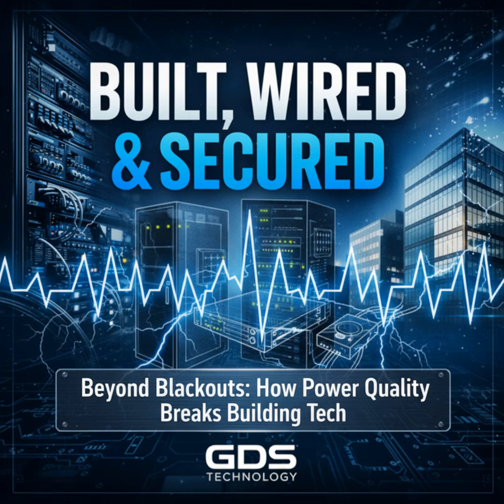Are there common mistakes you see when teams choose the wrong approach? Yes, the classic is treating the symptom instead of the cause. Teams add more UPS capacity to avoid reboots without addressing harmonics or grounding issues. The UPS hides the problem until it fails. Another is over-specifying centralized gear before collecting baseline measurements, which wastes budget. And a practical mistake? Not including power quality requirements in tenant build-out standards, which shifts the burden back to operations after the tenant moves in.